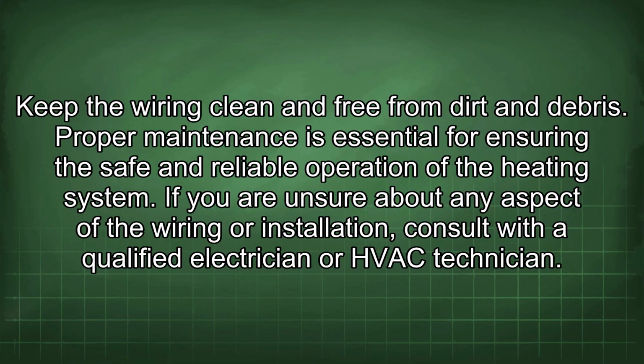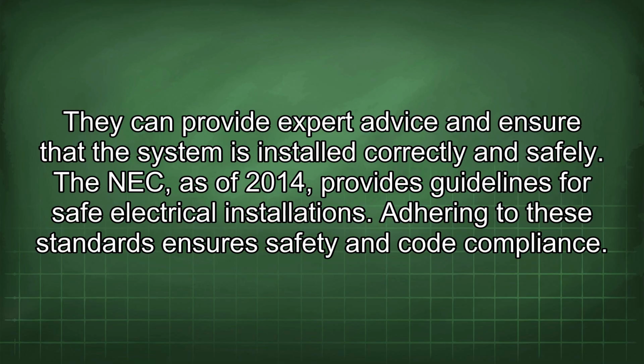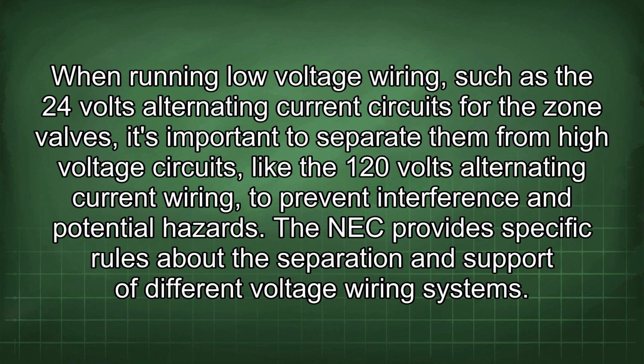If you are unsure about any aspect of the wiring or installation, consult with a qualified electrician or HVAC technician. They can provide expert advice and ensure that the system is installed correctly and safely. The NEC, as of 2014, provides guidelines for safe electrical installations. Adhering to these standards ensures safety and code compliance. When running low voltage wiring, such as the 24 volts alternating current circuits for the zone valves, it's important to separate them from high voltage circuits like the 120 volts alternating current wiring to prevent interference and potential hazards. The NEC provides specific rules about the separation and support of different voltage wiring systems.